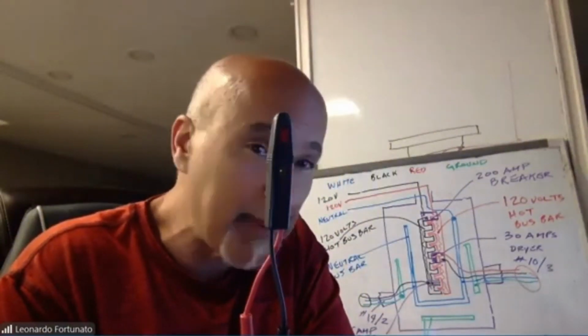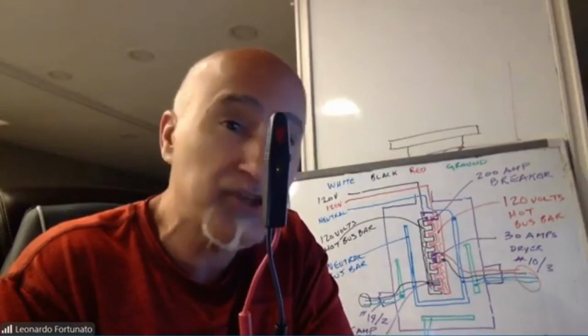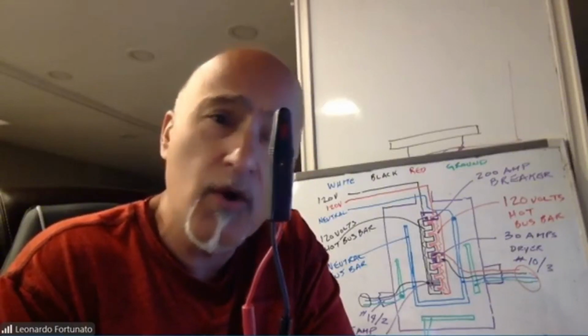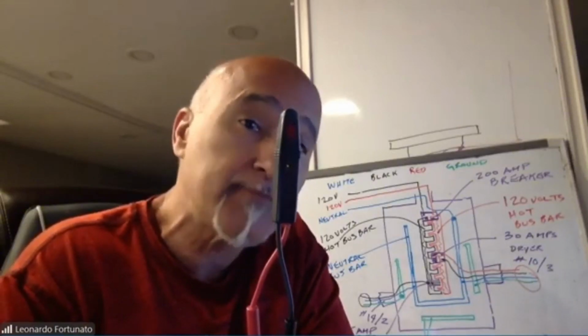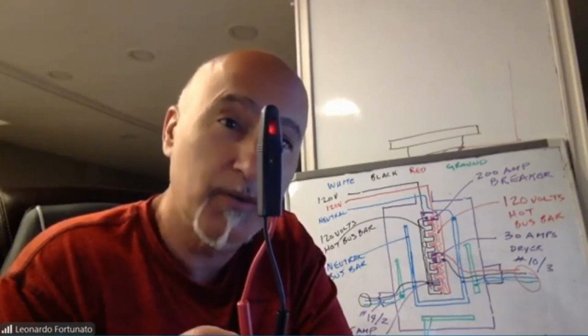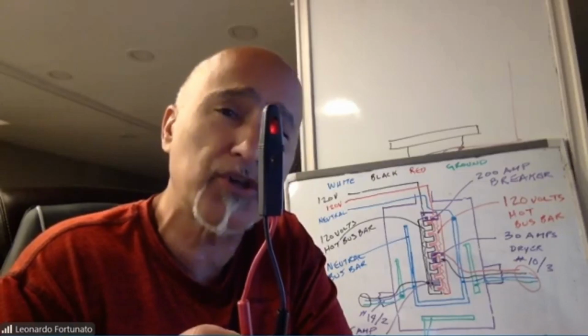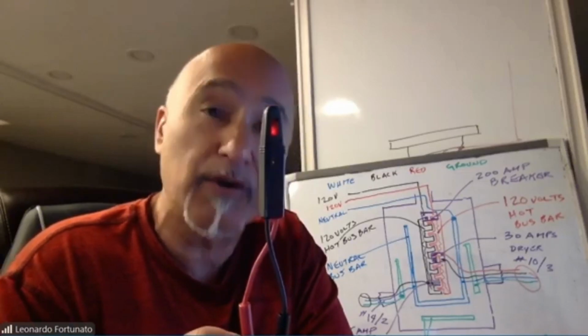Now, don't simply just think the power is off. Do yourself a favor: whoever turned the breaker off, tell them to turn it back on. We want to make sure it wasn't just you moving the tester, and that you still have good contact. So say, put the power back on. The light goes back on. Say, okay, turn it off. Now you know the power is off.